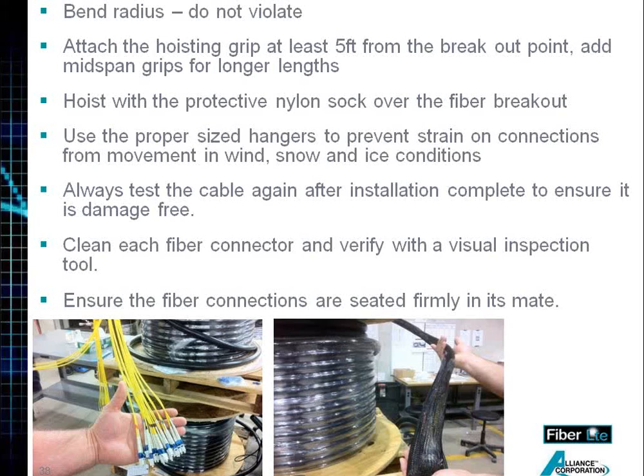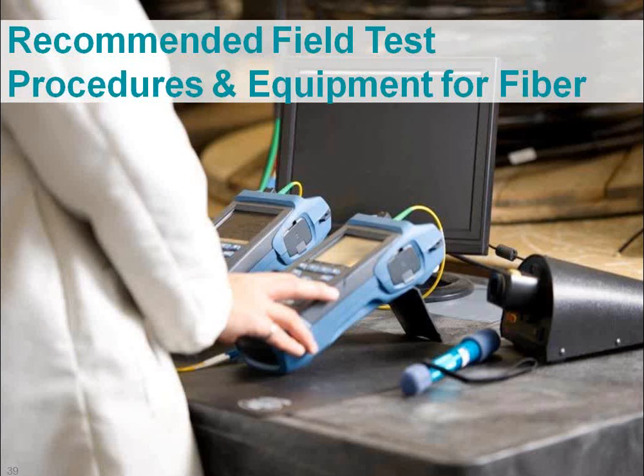Make sure fiber connections are seated firmly in their mate. When we use an LC duplex connector, when you mate it with its mate or in an adapter, you will hear an audible click when it's seated properly. If these connectors are not connected properly, the test reading will have a high loss or may even fail the cable. We've seen a number of cases where the cable is returned, only to find out there's nothing wrong with it, and through trial and error, it ends up that there's an issue with the mating connector or adapter. That's why it's always important to check and inspect mating connectors and adapters.